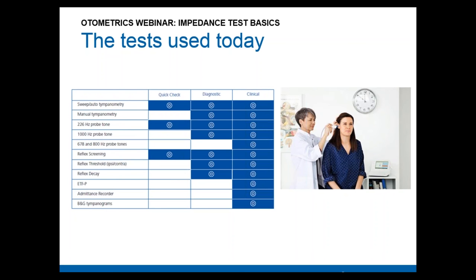Finally, in the high-end or clinical segment, you find all the tests described before, plus additional probe tones like 678 Hz or 800 Hz. You will also find tests for the Eustachian tube, B&G tympanograms, and the admittance recorder — a test that records admittance without stimulation. The industry generally provides increasing test packages across segments, with the high-end offering the most comprehensive set.